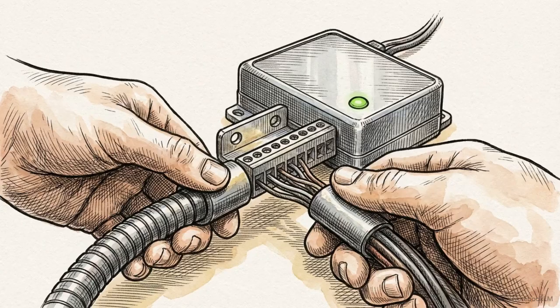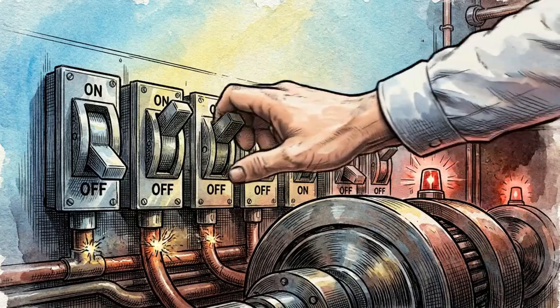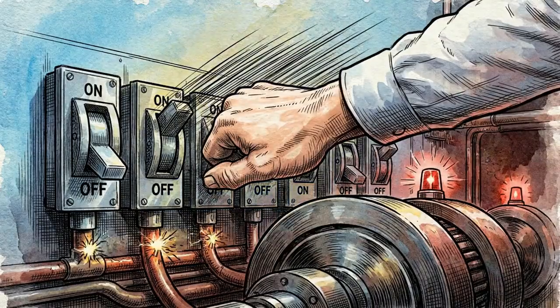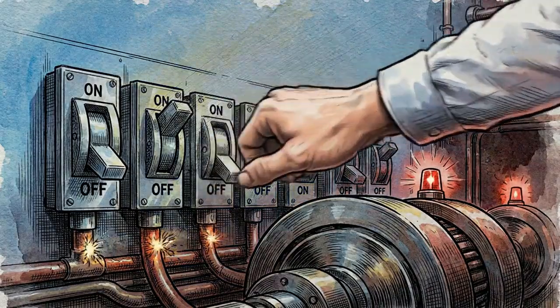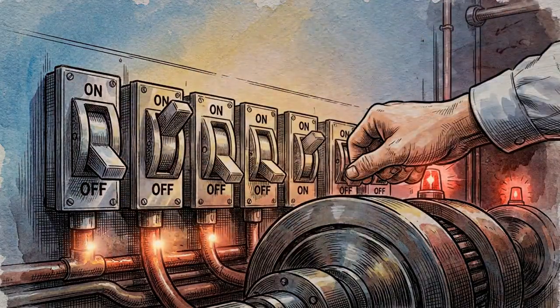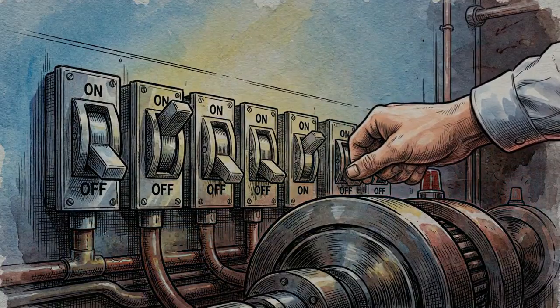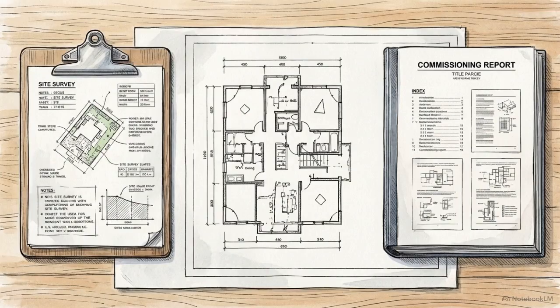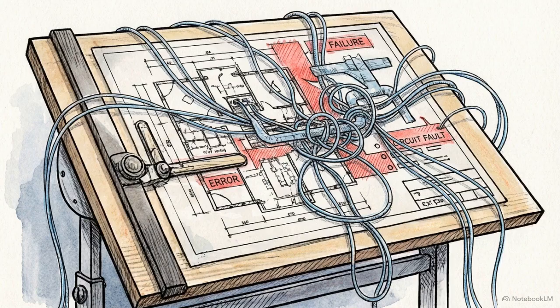The third step is installation and commissioning. After the physical deployment of wires and controllers, technicians execute rigorous fault testing, deliberately triggering system failures to verify the DDCs respond correctly. Designing a new BMS relies entirely on this deterministic workflow. Skipping the site survey or rushing the database design guarantees mapping errors and widespread integration failure.